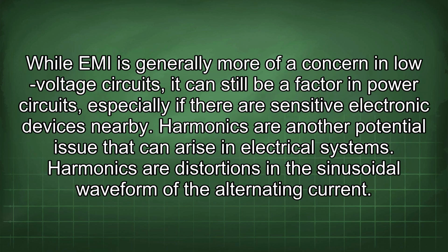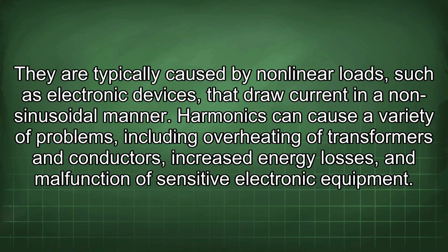While EMI is generally more of a concern in low-voltage circuits, it can still be a factor in power circuits, especially if there are sensitive electronic devices nearby. Harmonics are another potential issue that can arise in electrical systems. Harmonics are distortions in the sinusoidal waveform of the alternating current. They are typically caused by nonlinear loads, such as electronic devices, that draw current in a non-sinusoidal manner.